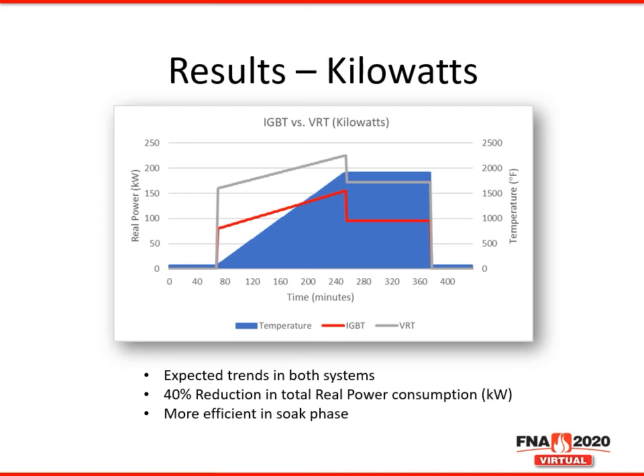This blue area is what was shown on the previous slide, where the furnace ramps up to a 1900 degree Fahrenheit soak phase. The two lines represent the kilowatt usage of the VRT and the IGBT MFDC power supply. This trend is what we expected to see. As the furnace is ramping up in temperature, it's going to take more energy, and at higher rates, the higher temperature you are at. And then when the furnace gets to a soak phase, the energy requirement drops to a plateau because we're simply maintaining heat. In this case study, we identified a 40% reduction in total real power consumption, or kilowatts, when comparing the two power supplies.